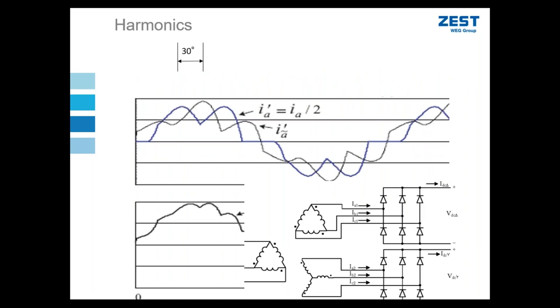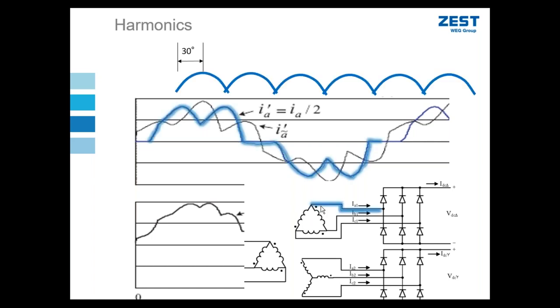Okay, we've looked at the voltage. So again, we're going to break down what happens with the current on the input. If we were to measure the current on the input of one phase of the first rectifier, it is what is represented in blue. I've just kept the six pulse voltage waveform up there for reference, but the current waveform would look like what is in blue. So you can note the similarity of that current waveform to what we already showed for a standard six pulse rectifier. And then the same occurs with the other, with rectifier number two, shown in green. I have a similar bunny ears distorted waveform measured in one current.